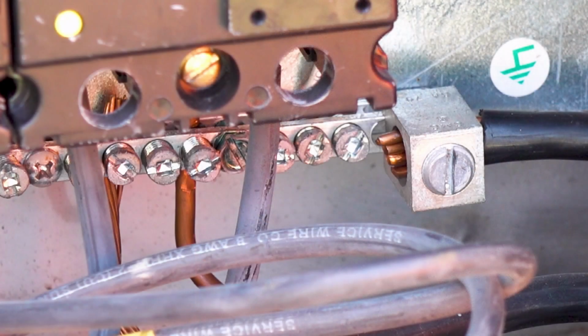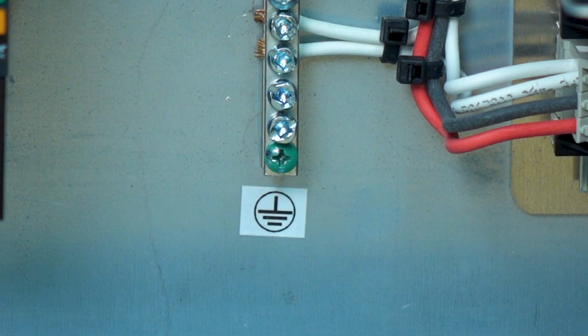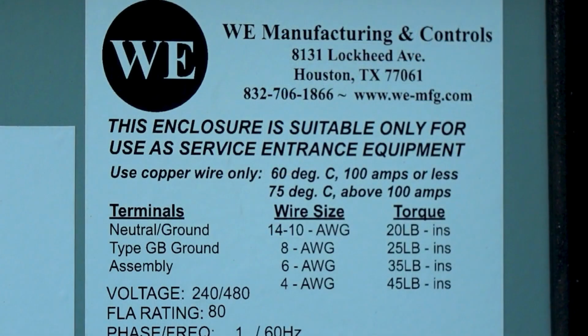Additionally, all green or bare equipment grounding conductors will terminate to this bus. The bus bar will be bonded to the service enclosure with a green bonding screw according to NEC standards. A label near the bus bar must show the correct torque values for the screw lugs that terminate the conductors to the bus bar.